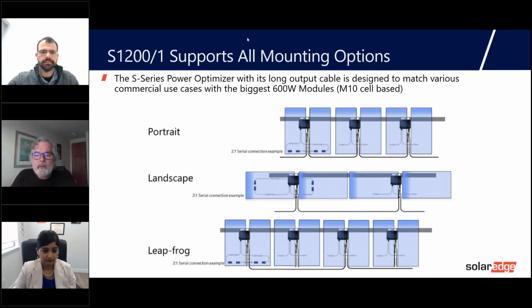Okay, on this slide, we have some images that show how things connect at the string level. In the top row, we have modules in portrait orientation, and you can see how they're connected on the input side of the optimizer. One of the input leads would connect to the first module. The two modules would connect together in series, and then the other side of the second module would return to the input connector on the optimizer. And as Clever mentioned, we have a short lead on the output side and a very long one, right around 17 and a half feet for the long one. So in portrait orientation, there will be a little extra cable to coil up and manage, but they're connected.